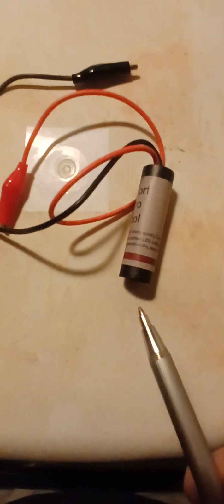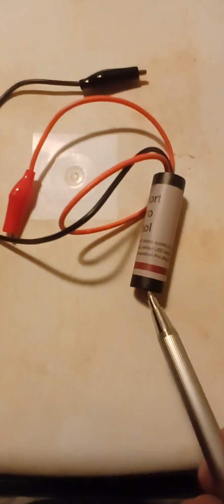To recap: remove the fuse, clip one alligator clip where the fuse went on the board, clip the other one on the other terminal, and run through the system. When the short's light comes on, say it's in the Y wire, you know that wire runs to the air handler and sometimes out to the condenser, so you'd follow it back from there to the outside condenser, then follow the schematics, getting the wiring diagram if available.